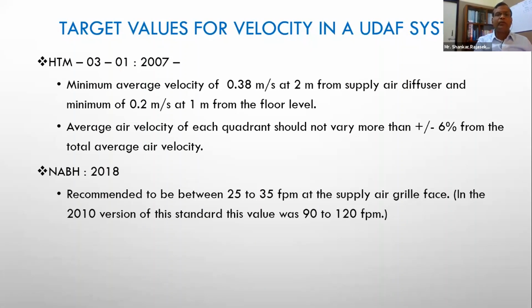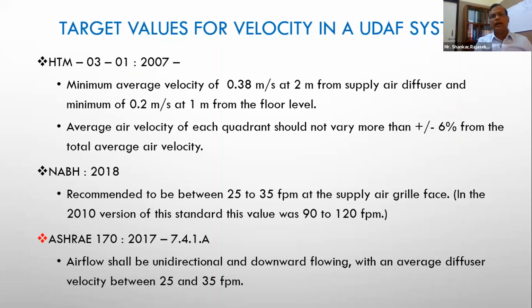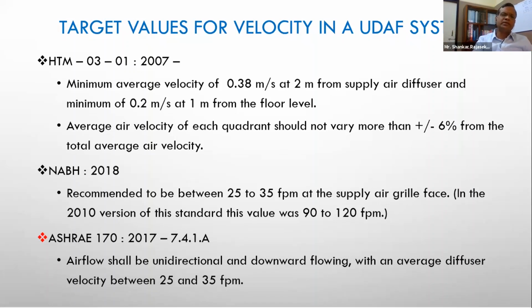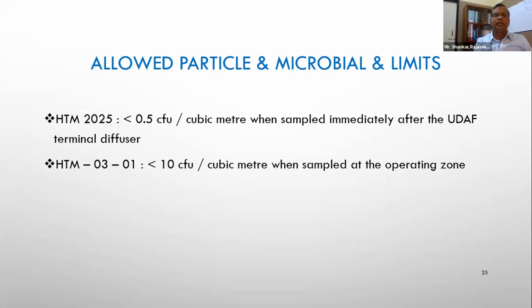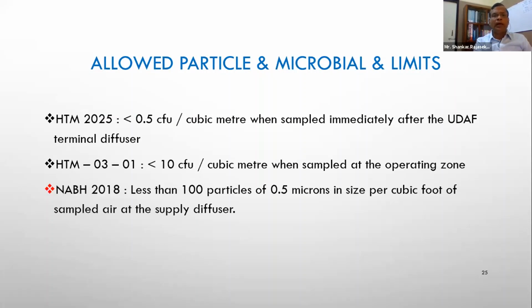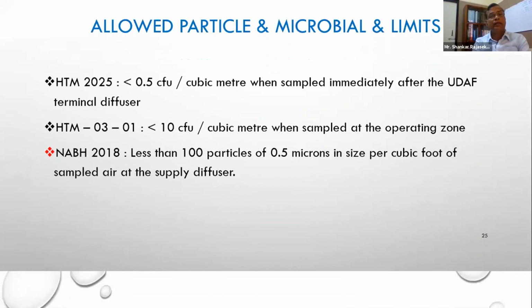NABH talks about 25 to 35 feet per minute. But this value was earlier 90 to 120. They have now been revised. ASHRAE also talks about 25 to 35 FPM velocity, but this is all at the supply grill. HTM is the only one which says what values have to be there at 1 meter from the floor level and 2 meters from the supply diffuser. That's why I said the HTM standard becomes very, very specific and particular. So these are the allowable microbial limits: 0.5 CFU at the terminal diffuser and less than 10 CFU on the operating table. The NABH does not talk about microbial values. It talks only about particles, and it says less than 100 particles of 0.5 microns in size for every cubic foot of sampled air at the diffuser.